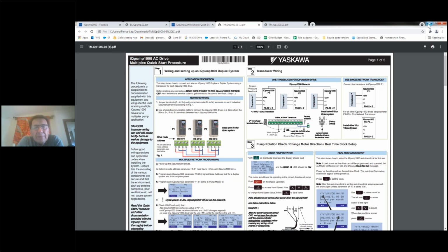But the inverter duty cable has manifest benefits in terms of life of components, especially the motor, but also all of the instrumentation in the environment, because the inverter duty cable, because of its shielding and its hopefully geometric symmetry, if you choose the symmetrical cable design, which is 3 phases of conductors and 3 reduced size grounds, and I'll try to find a picture of that in a second. What do you get back for that 50% increase in the cable cost, which, by the way, turns out to be insignificant in the total installation, in the cost of the total installation?